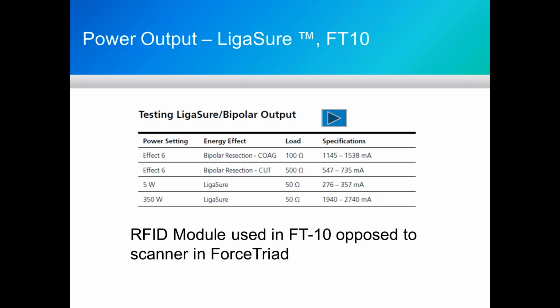Testing here is a little bit different than what you did on the Triad as well. There are 4 tests: bipolar resection, LigaSure at 5 watts, LigaSure at 350 watts. We're going to do the 350 watt test, and our range of current is 1940 to 2740 milliamps. Difference here with LigaSure is we're going to use 50 ohms as our test resistance. And I'm going to do this test in the RF mode.